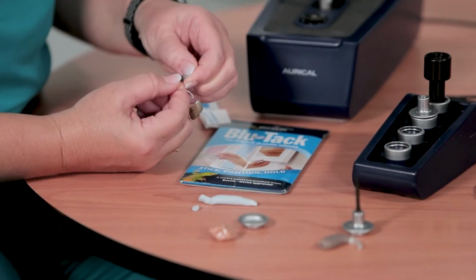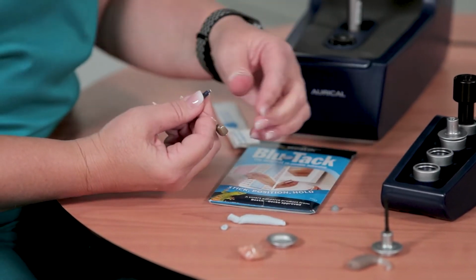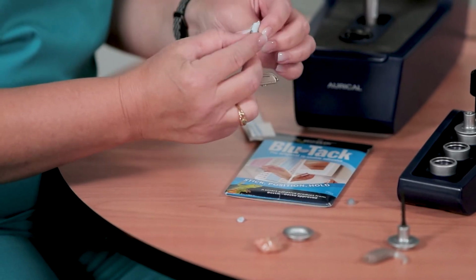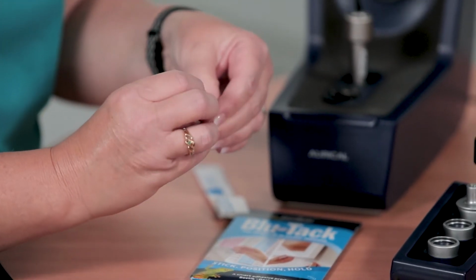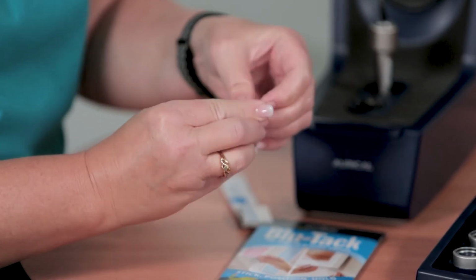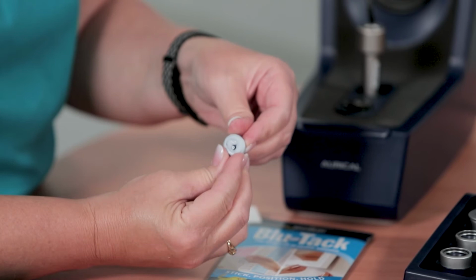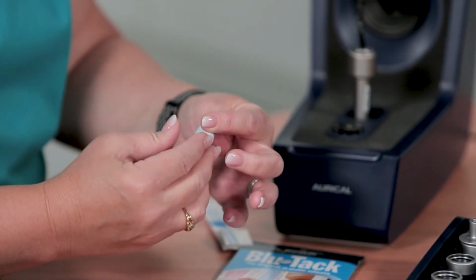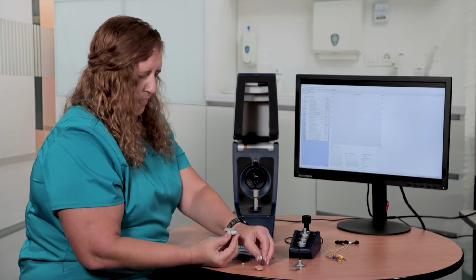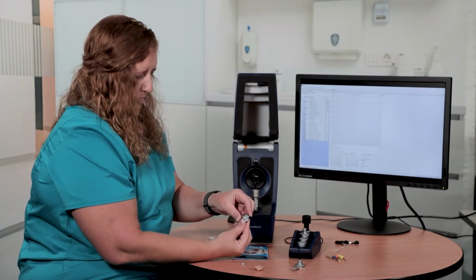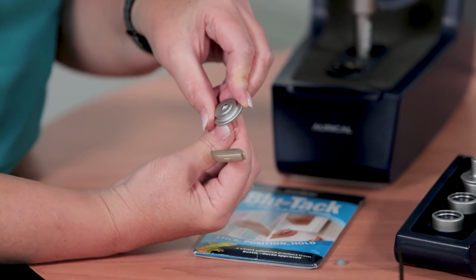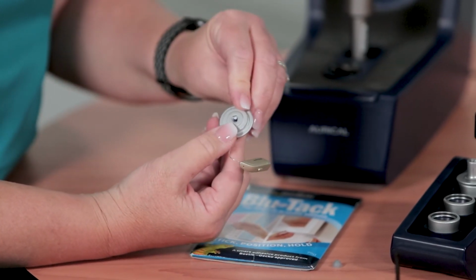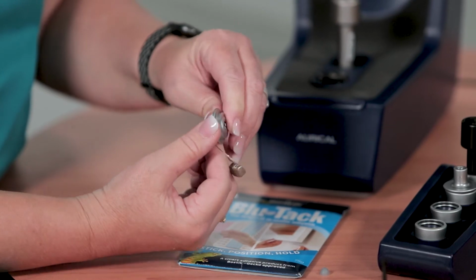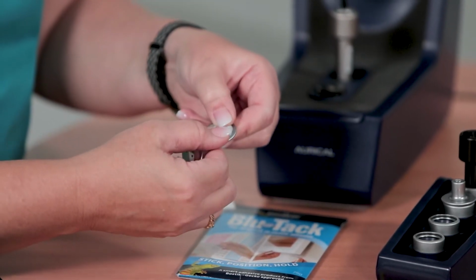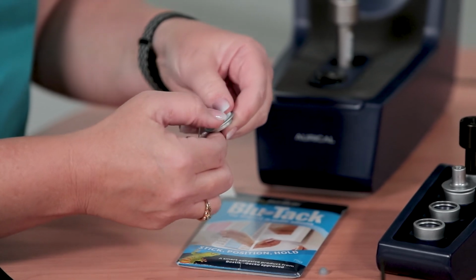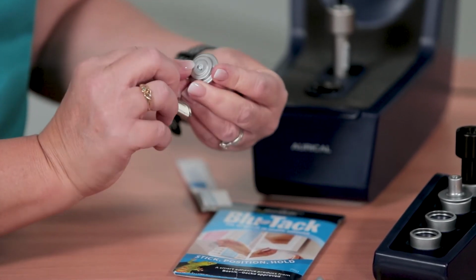Create a tight seal with the acoustic putty by wrapping it neatly around the acoustic opening of your hearing aid, such as the end of the thin tube or opening of the receiver. For custom in-ear hearing aids, this would be the opening of the receiver port on the custom shell. Continue to wrap the acoustic putty around onto itself to create a circle that can be placed on the HA1 adapter. Carefully line up the acoustic opening of the hearing aid to the hole in the center of the HA1 adapter, and then press securely to ensure there are no gaps and the coupling to the adapter is well sealed.